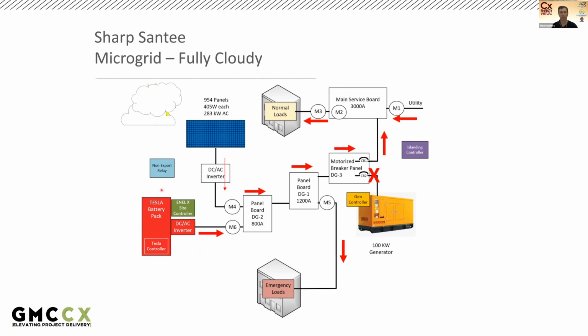Here's where the non-export relay will throttle the Tesla battery export so that meter M6, like I said before, doesn't exceed meter M3 minus M4, which is the available power to normal loads after taking into account any solar power produced. So power is supplied to the building normal loads, but not enough, by design. Then any additional power is brought in from the utility.